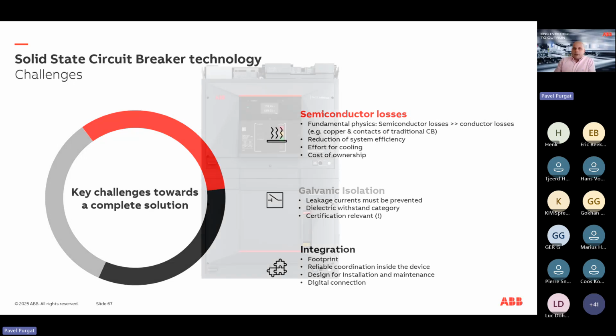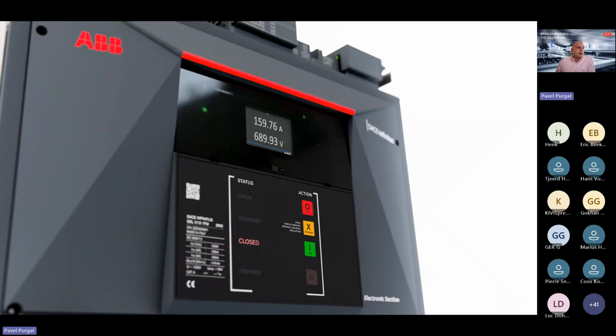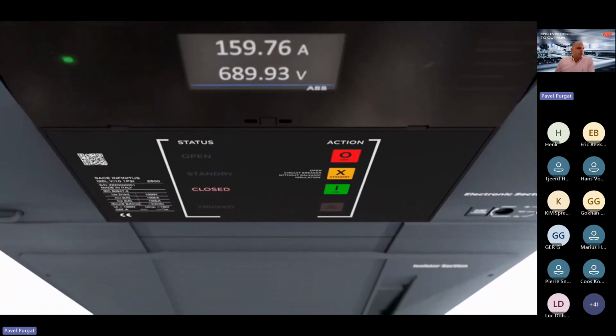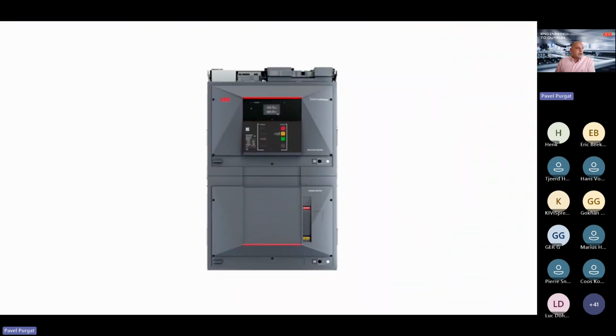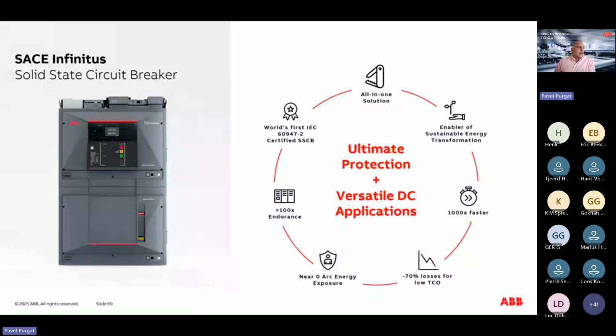And the first IEC certified semiconductor circuit breaker is right here. It is the Sace Infinitus. The team that developed it can be very proud of their achievement, because they were the first to actually manage to get the proper certification as a circuit breaker, which means it can be deployed in systems in the IEC world. Also, because of integrating all the functionalities, it can act as a circuit breaker, contactor, switch, or isolator. It enables sustainable energy transformation because it enables DC systems, or systems that are much more efficient.